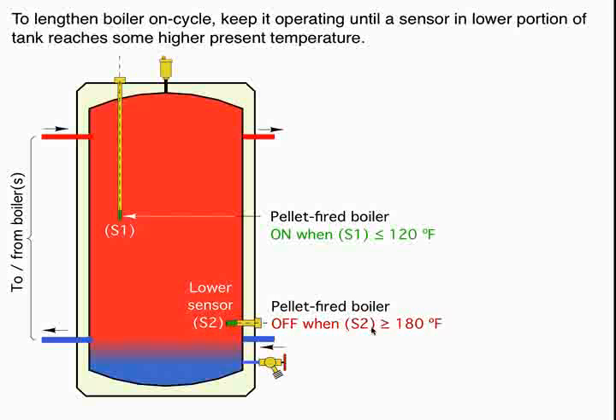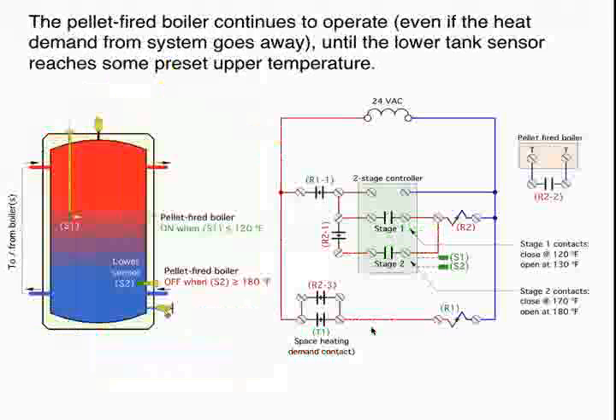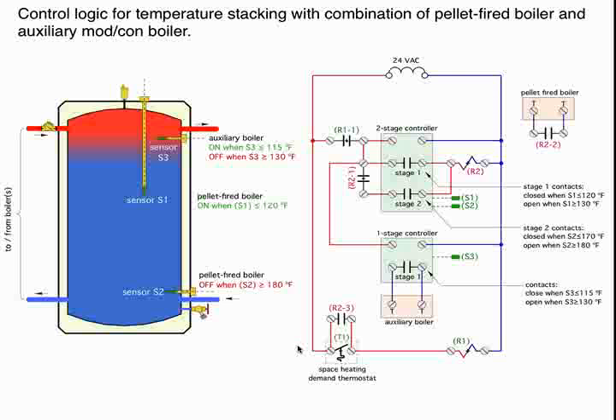So, it's kind of a unique strategy. I ran into this a couple of years ago looking at controls from a European manufacturer for pellet-fired boilers. And at first I wasn't quite sure what they were doing, but think it through and it makes a lot of sense. I don't want to take a lot of time to explain this, but you can create this strategy using a two-stage set point controller. You can also do it using a two-stage reset controller. Some pellet-fired boilers include the control logic to do this right in their internal controller. So you don't need to create any kind of external control logic to do this. But this combination of a two-stage set point controller and a couple relays basically allows you to have two different set points, one for an on condition and one for an off condition.